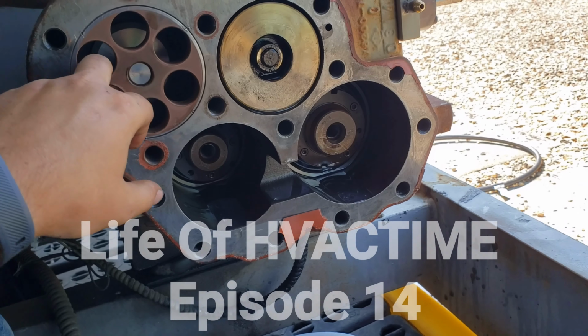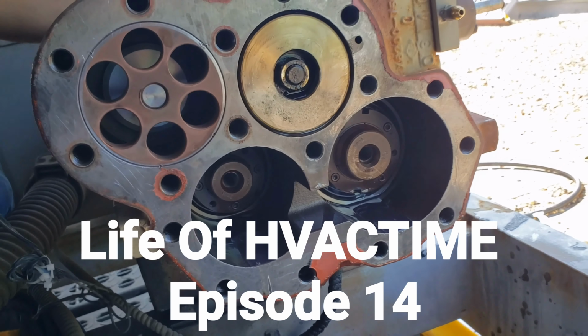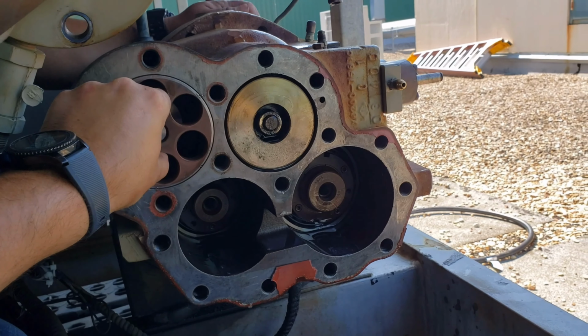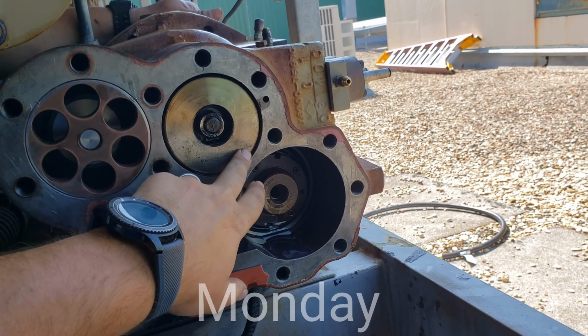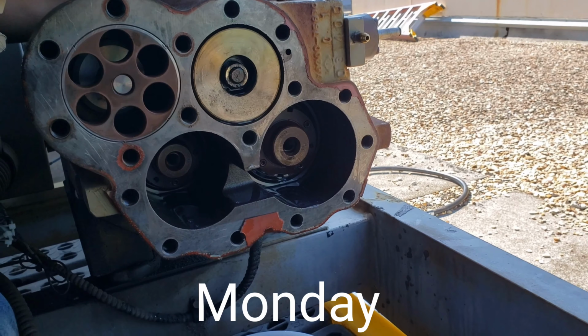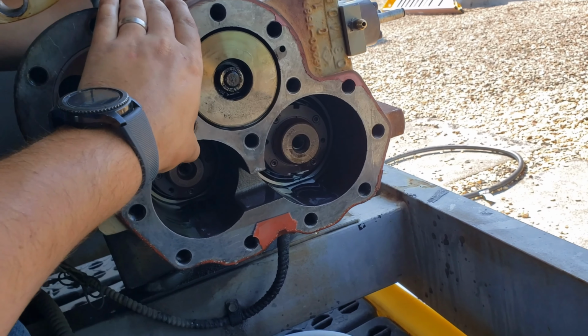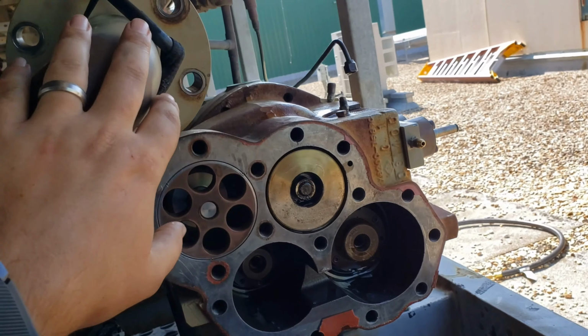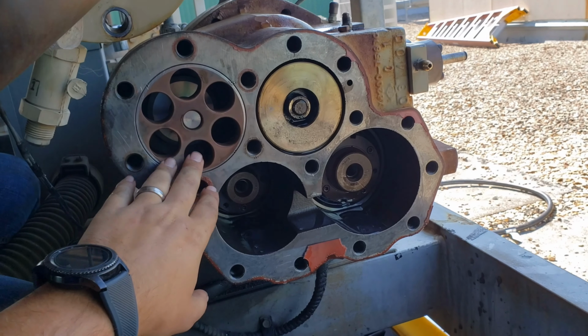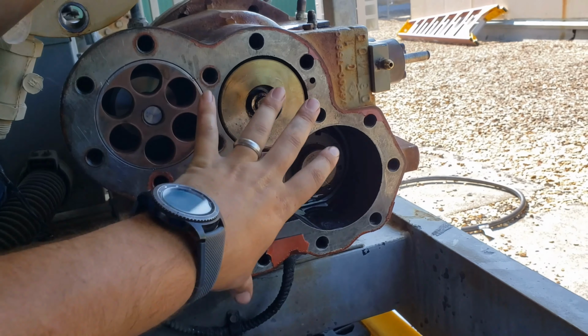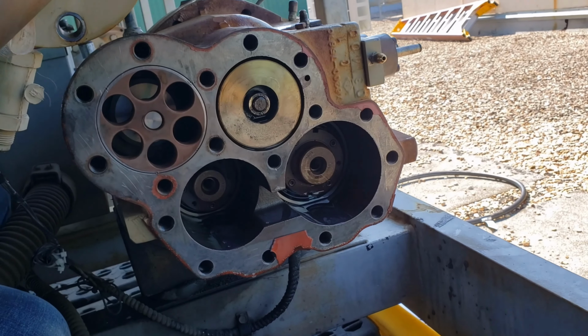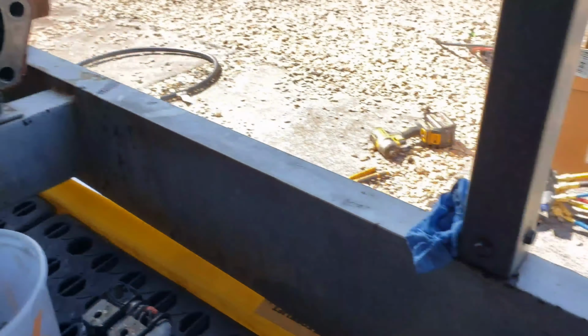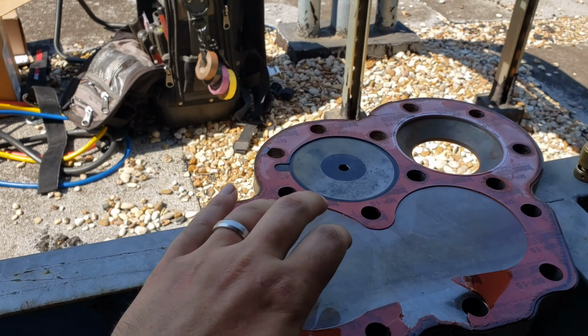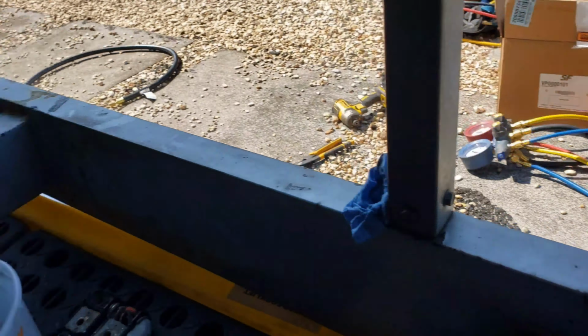Alright guys, so we're here doing a gasket change on this RTAA screw. We've already isolated just the compressor on its own. We've got the discharge pulled up out of the way. We're going to be taking this whole assembly apart, changing the O-rings and the gaskets. You can see that there's one of the front covers there.